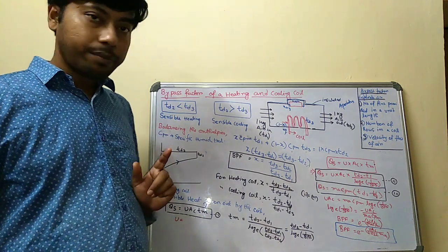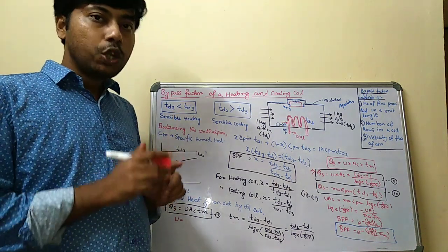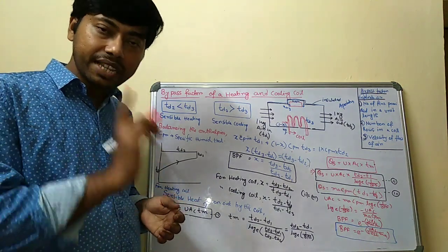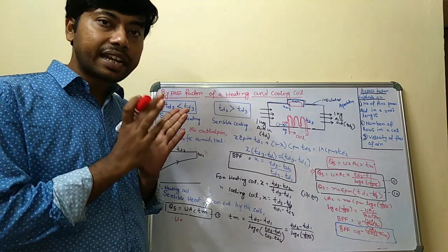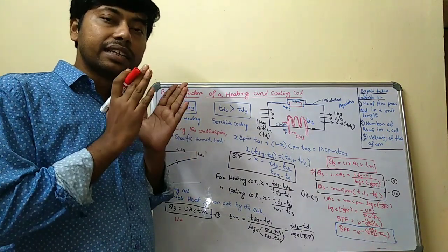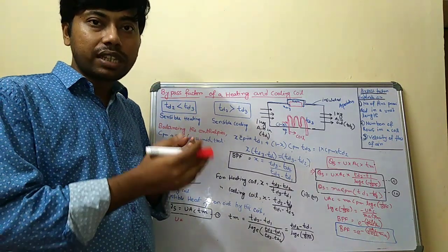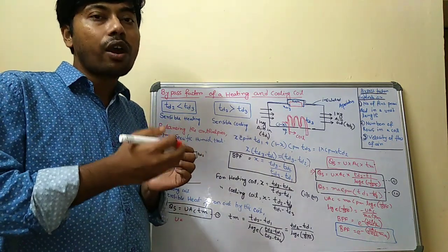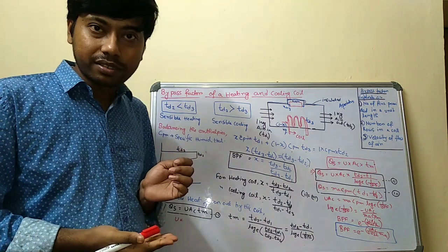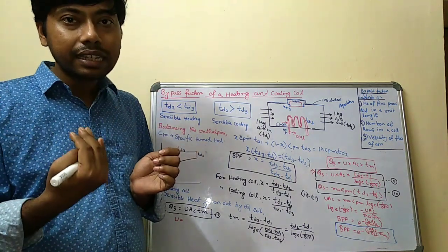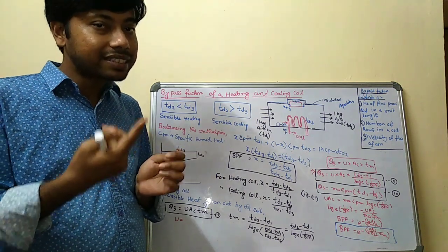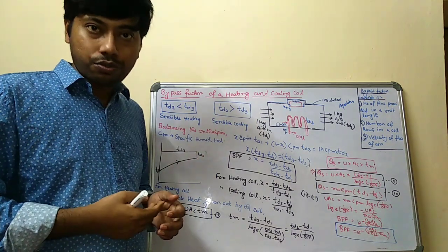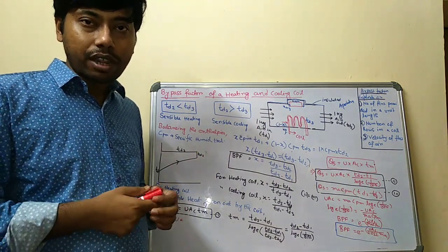But one more important point: a low bypass factor indicates better performance of the coil. Very important, note that point. If the bypass factor is less, that indicates the coil gives you better performance. If the bypass factor value is high, then the performance is poor, or bad, you can say.